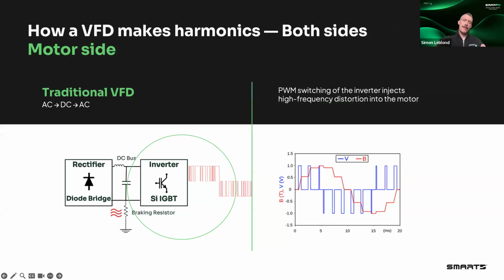Now, we've talked so far only about harmonics on the grid. As I mentioned, they have the same impact on the motor, and they do exist on the motor, caused by VFDs. The mechanism is not exactly the same, though. On the motor side, it is the IGBT inverter that causes the harmonics, and this is the switching. Typically, an IGBT inverter in a VFD will be switching at 2, 4, maybe 6 kilohertz to produce a pulse width modulated waveform, or PWM. So it's not a sine wave. You can see on the right side of my screen these voltage pulses in that pulse width modulated waveform.